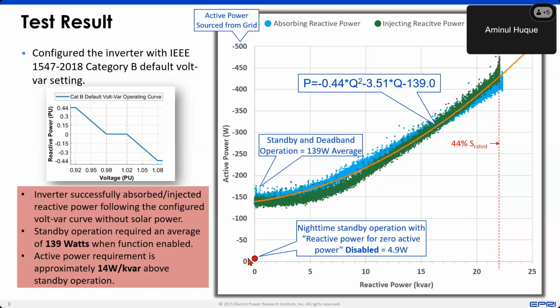So this is a 50 kilowatt inverter. During nighttime sleep mode or standby mode, it takes 4.9 watt. But if we activate this function, Q at 0 active power, basically nighttime VAR, it was taking roughly 139 watt. So you can see clearly a change. There is an active power demand, even if you don't get any reactive power out from the inverter, just to keep it operational. There is a cost, roughly 135 watt additional is needed just to keep it on for the whole night. And then the more VAR we request, whether absorbing or injecting, the more real power is needed.